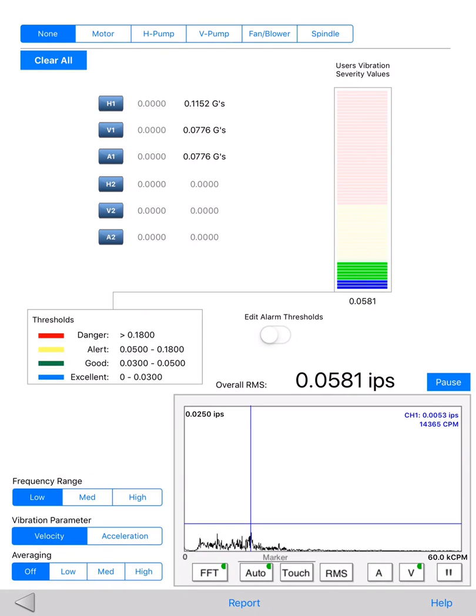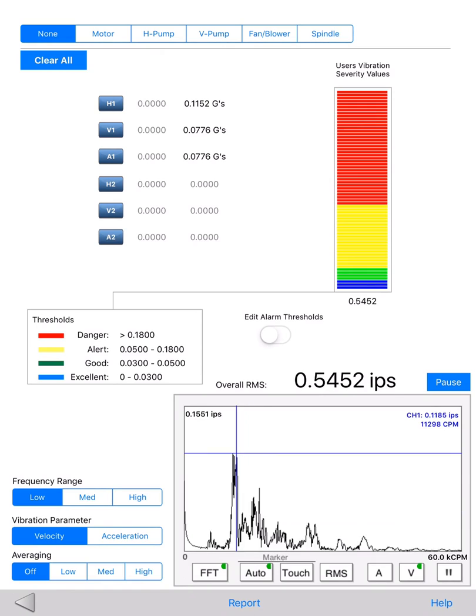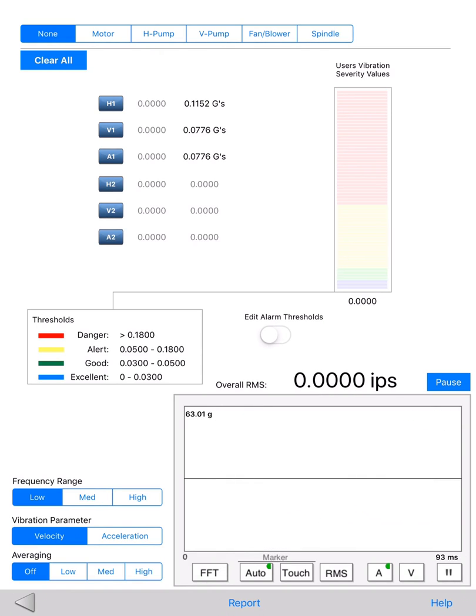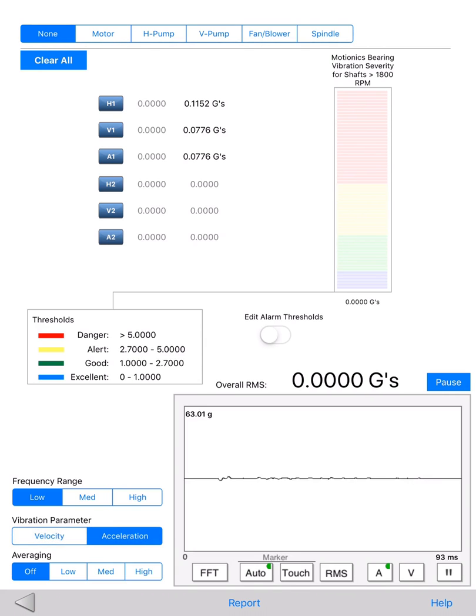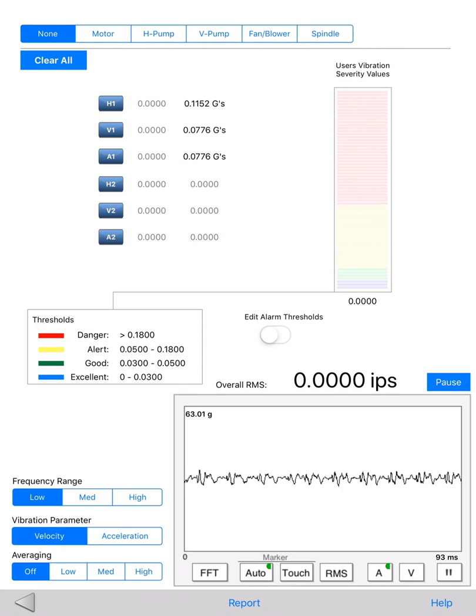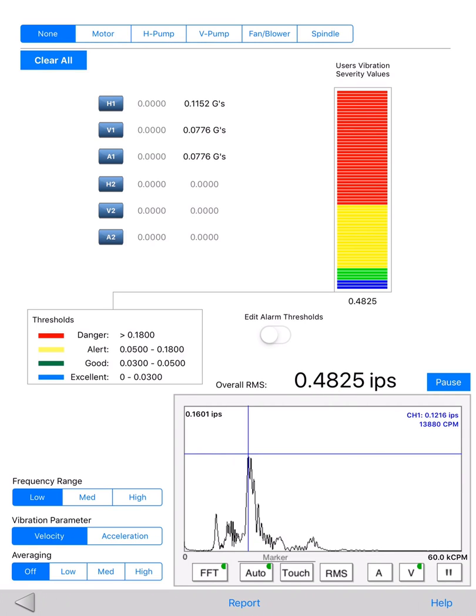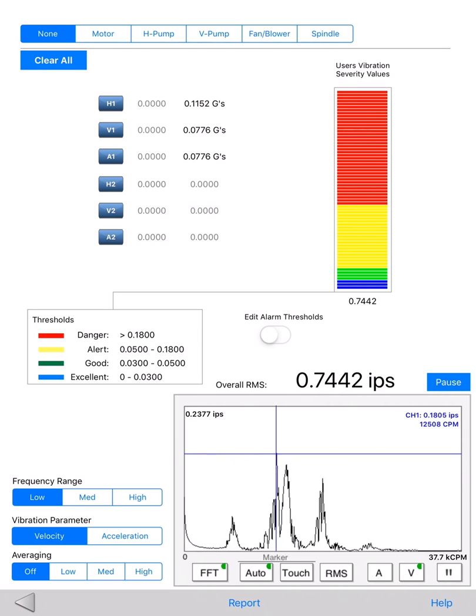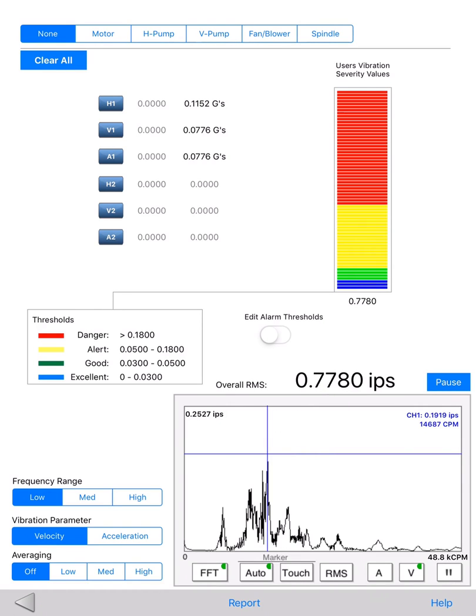If a custom standard is required, or measurement is based on acceleration, the user can simply tap on the text field and enter a threshold value. The bottom part of this page consists of a real-time signal viewer. It continuously updates vibration signals in time waveform or FFT spectrum. Acceleration signal from the accelerometer is used directly for analysis or integrated to velocity. You can use two fingers to pinch to zoom to a specific frequency range, or quickly use the selector on the side.